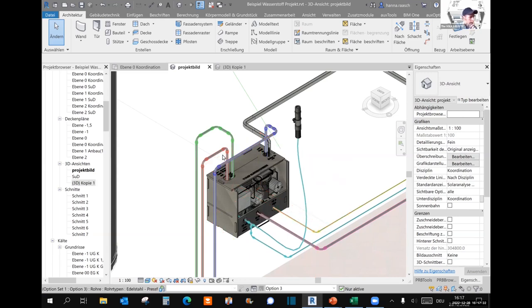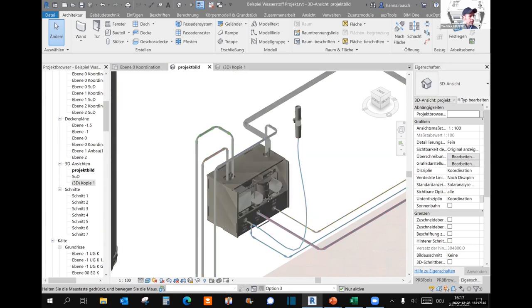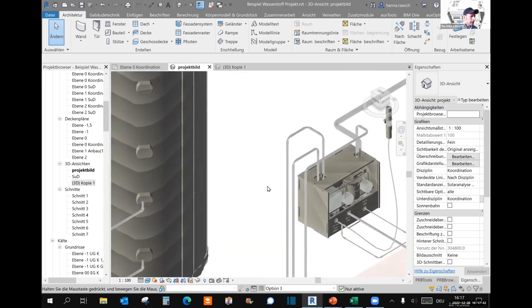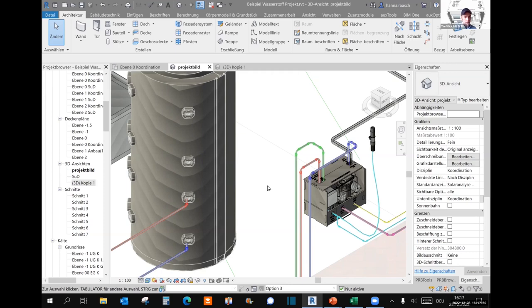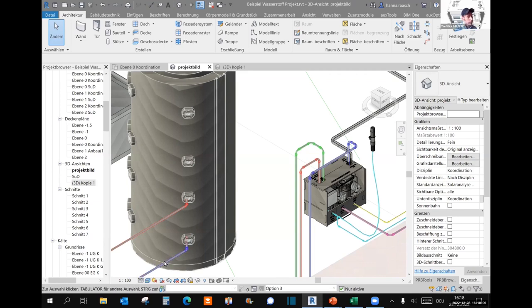Besides the process, the electrolyzer will produce heat and it is very important that we get rid of this heat. That is the red and the blue pipe which goes directly into your buffer tank. Most buffer tanks of my clients have many ports. Some are used for thermal solar, some are used for the heater itself, whether it's a gas boiler or whatever. The heater will be traditionally far up because it has high temperatures.